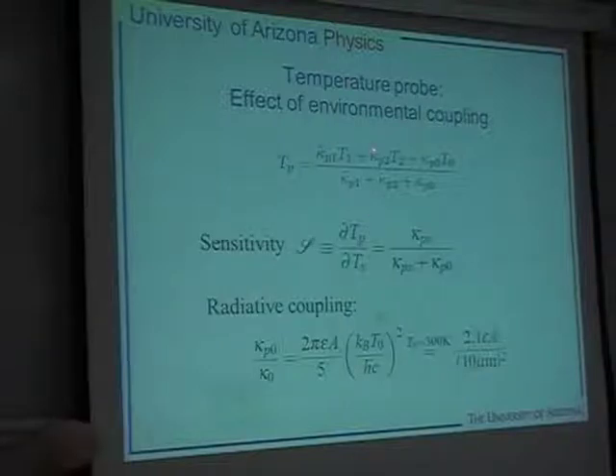I've told you how we calculate these conductances. As for the one involving the environment, it really depends on the nature of the environment and how it couples to the probe. If you buy a commercial scanning thermal microscope, the dominant contribution is just convection through the gas between the tip and the sample. If you go to ultra-high vacuum, in principle you might be limited by radiative blackbody coupling between the probe and the surrounding blackbody radiation.